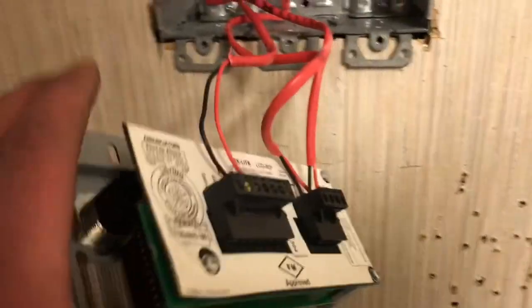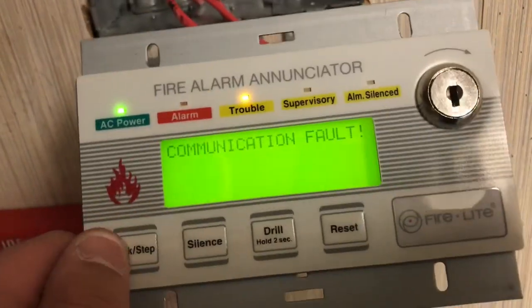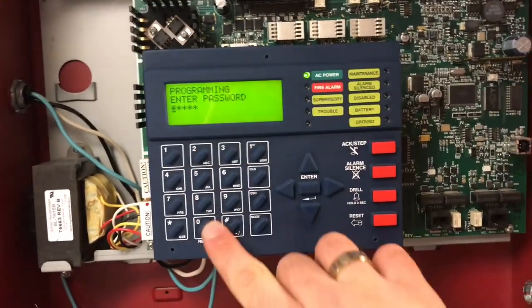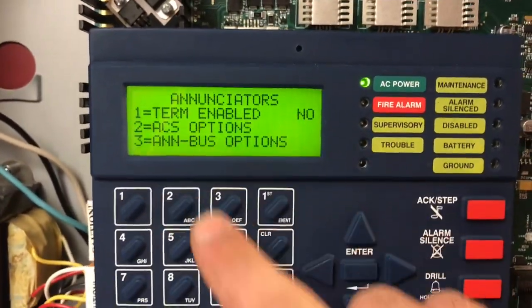Our annunciator is wired correctly — we have the correct wires on the correct terminals. Now we have to program it into the system. It currently says 'communication fault.' Coming to the panel, it says 'system normal' — it doesn't see the annunciator yet. I'll press Enter, then 2 for programming with our default passcode, then 3 for option modules, then 1 for annunciators term enabled. Now the annunciator is online with the system — anything the panel reads on the LCD will happen here at the same time.